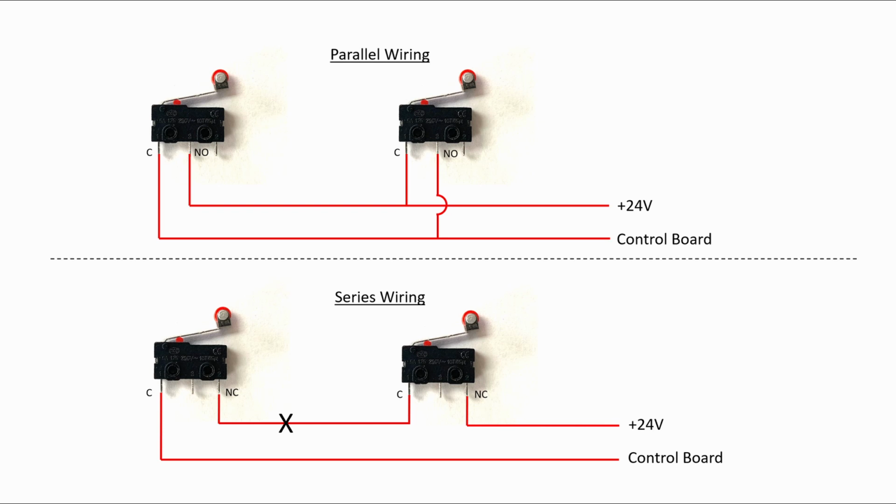This happened to me when one of the wires on one of the switches broke, something bumped against it, and the circuit opened and the machine wouldn't run anymore. I then had to go looking throughout the whole system to find out where the problem was. But at least I knew that there was a problem, rather than it not showing itself when the machine tried to over-travel and then wouldn't trip the limit switches.